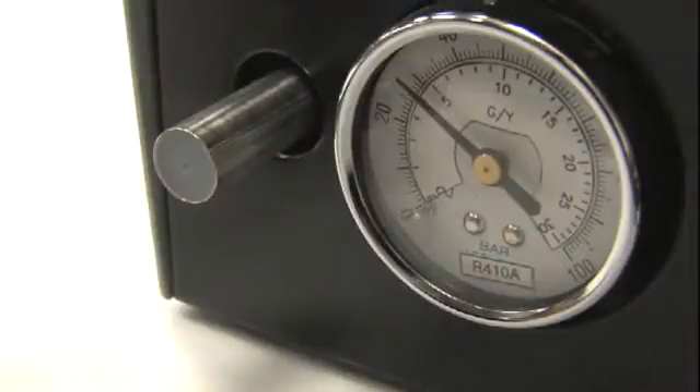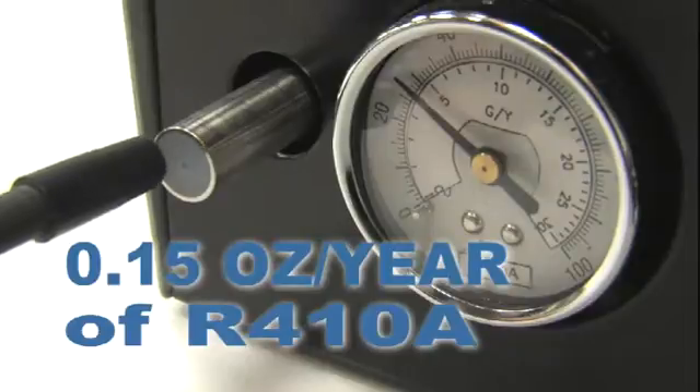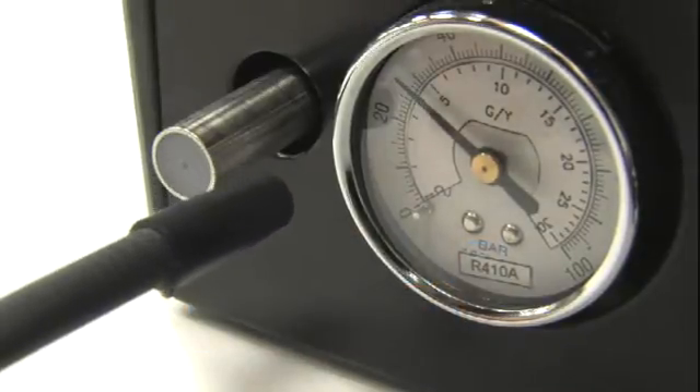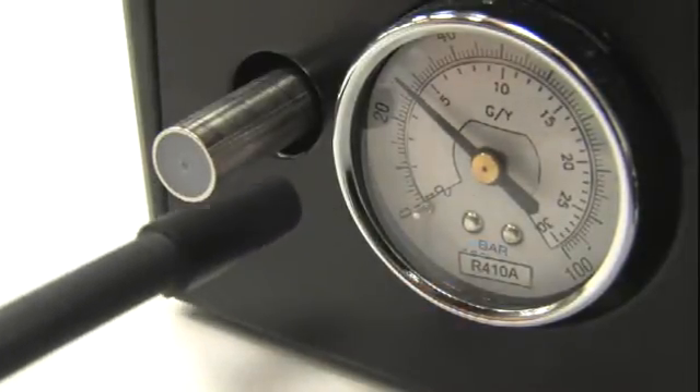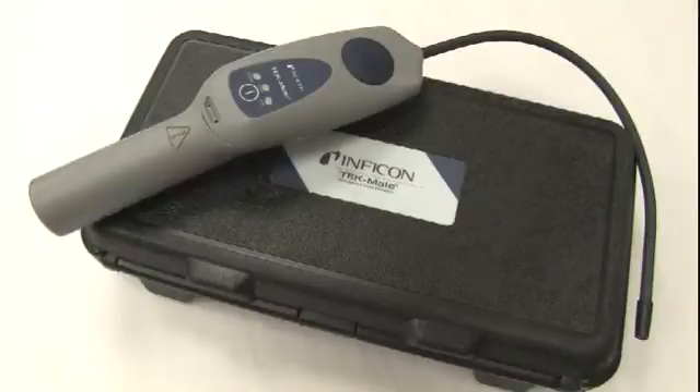It's also very sensitive. This is a 0.15 ounce per year leak of R410A and TEK-Mate detects it immediately. This leak size is even smaller than the minimum guaranteed sensitivity of a quarter ounce per year, and it's the kind of sensitivity you can expect from TEK-Mate on the job site.